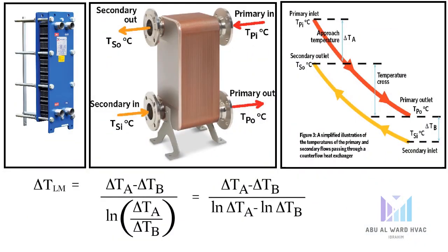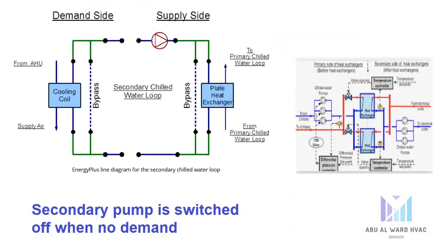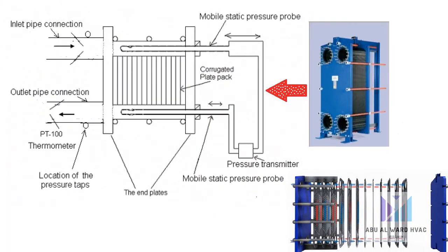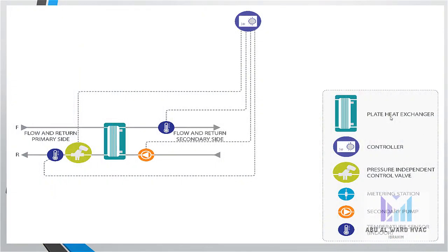Benefits: the PICV ensures balancing of the primary flow and eliminates the use of both static balancing valves and differential pressure control valves, providing an authority of 1 for the plate heat exchanger control. Return temperature on the primary side is secured. Secondary pump is switched off when no demand. Considerations: minimum differential pressure required for the PICV must be available at design flow. And this is the schematic for this case.